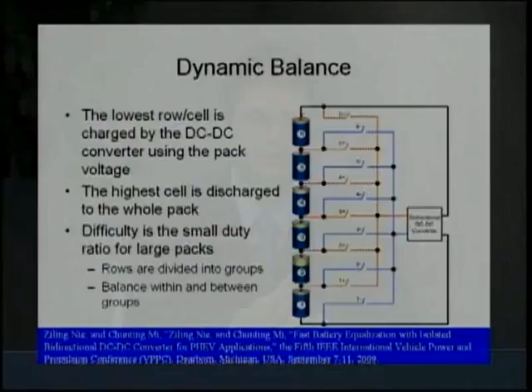So in that case, the best way is to do a dynamic balance. A dynamic balance of battery is similar to the capacitive balancing and inductive balancing mentioned earlier. It's a very complex system to design, including the switches, switch control, switch arrangement, and the size. In order to reduce the overall size and simplify the control, we developed a bidirectional DC-DC converter-based dynamic balance. In this system, we have a number of switches, but only one DC-DC converter instead of many capacitors or a multi-winding transformer.